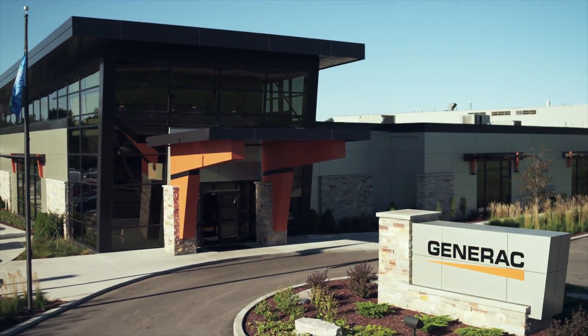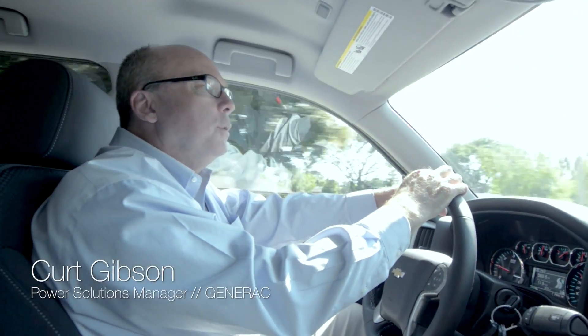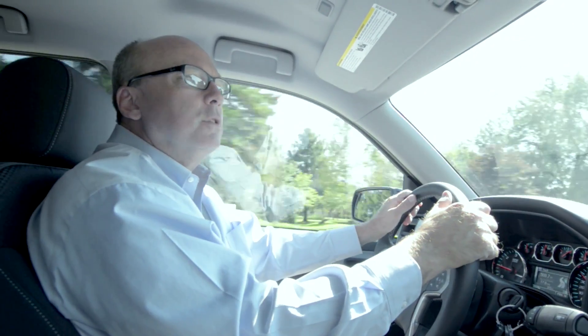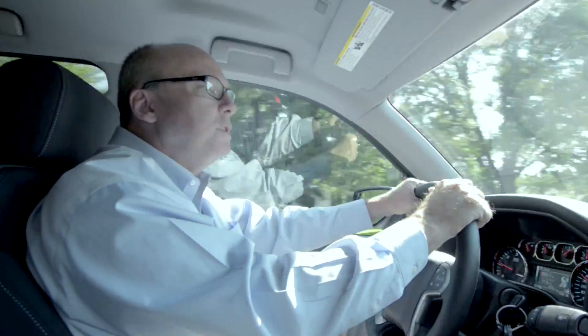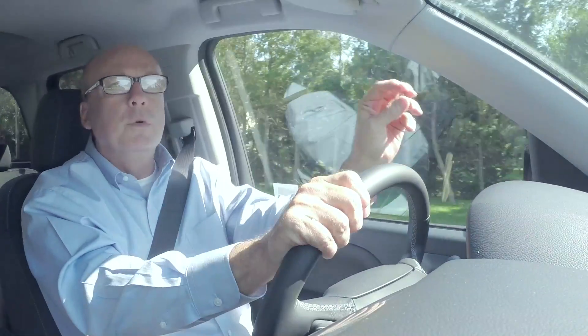Mike Ballas originally had a design that showed redundant buses, but he didn't have a control scheme. In other words, by putting the controls in each one of the buses through using traditional paralleling, they would have had to hand off that control from one switchgear lineup to another. We were able to keep the controls all off the central point on the generator, so there were really no controls in each one of the switchboards.